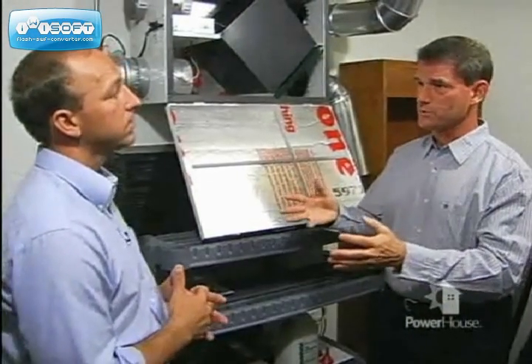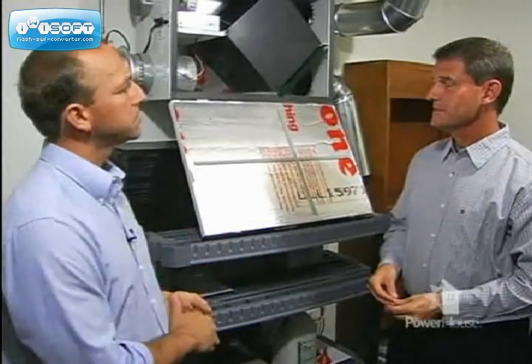You've mentioned energy efficiency a number of times with the HRV. What can I expect in terms of energy savings? The HRV is going to recover 70% to 80% of the heat or energy from the stale air it's exhausting. Most units use around 100 watts of power — to compare, a light bulb in your living room uses about 100 watts. By building an energy-efficient house, you save 2,000 to 4,000 watts of power, so installing one of these only uses around 100 watts. That's sizable energy savings.